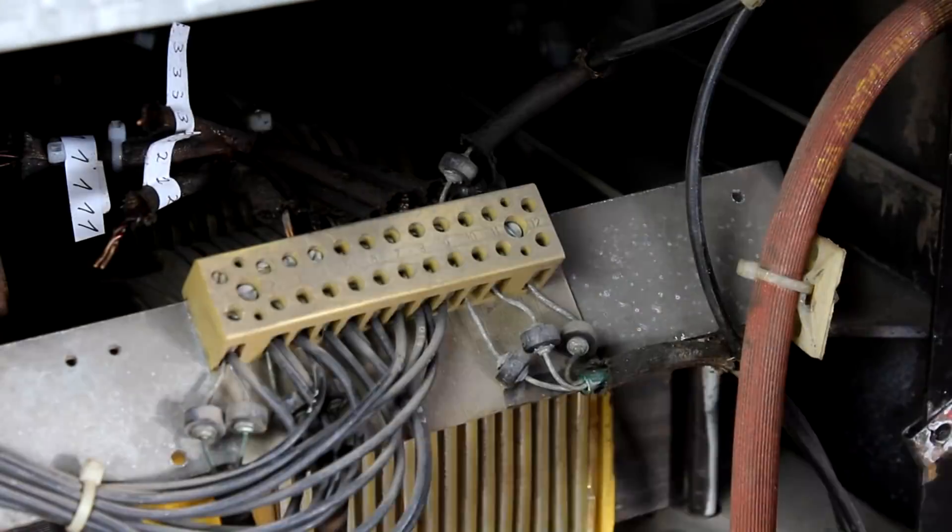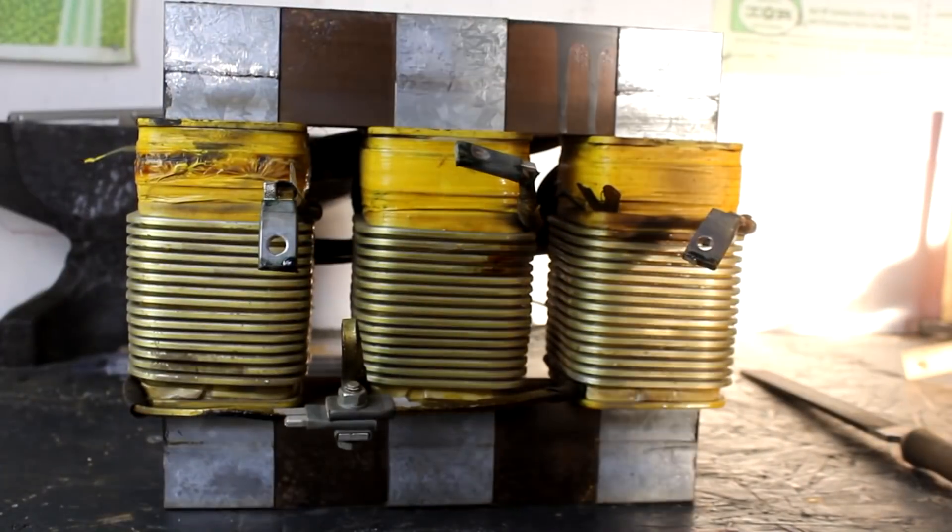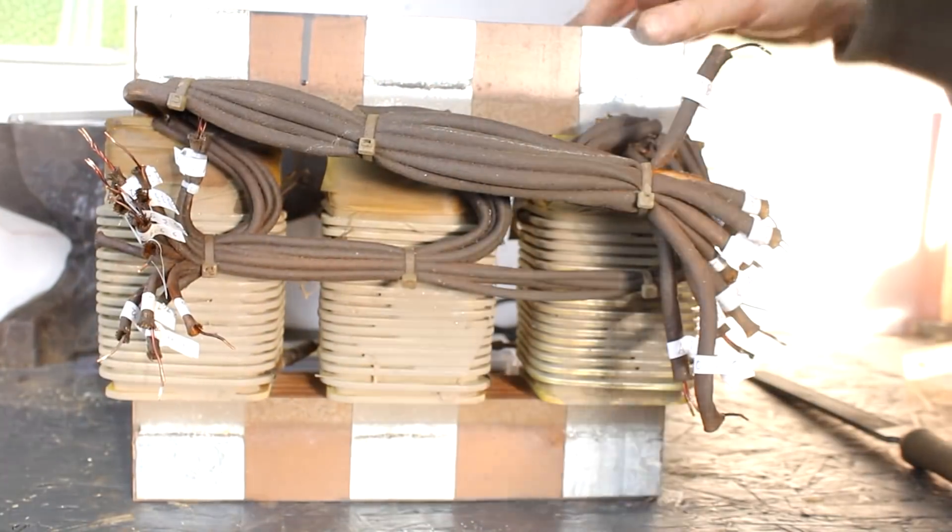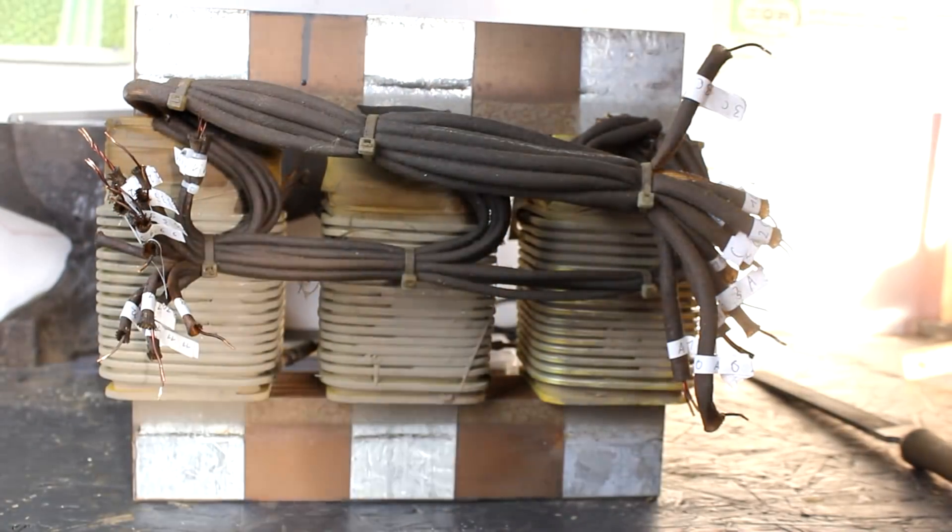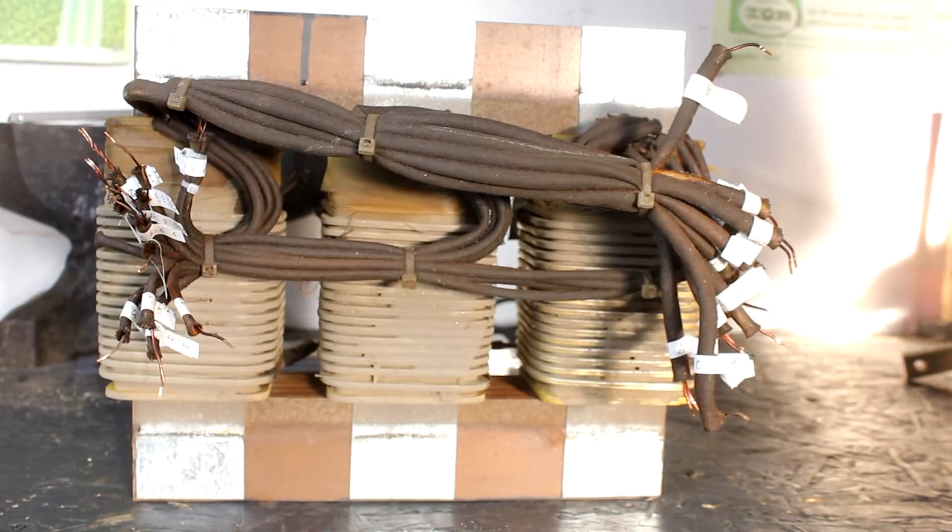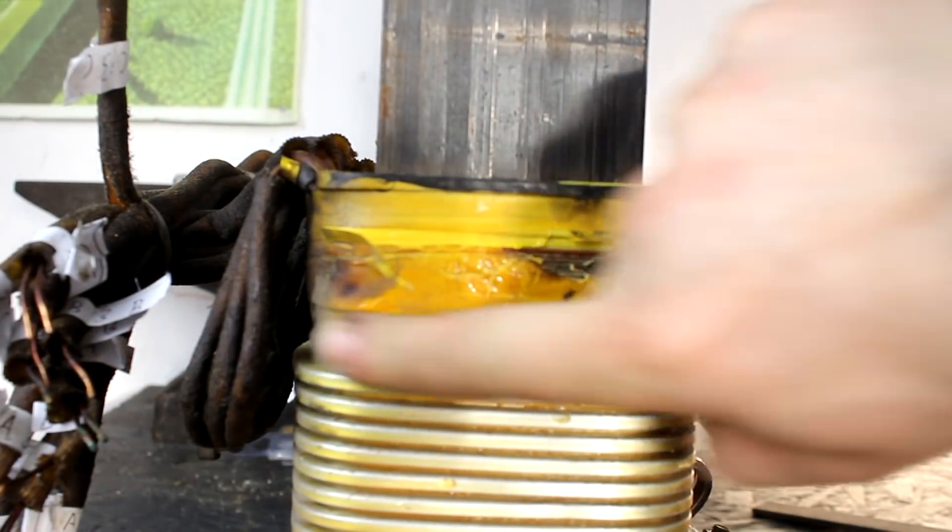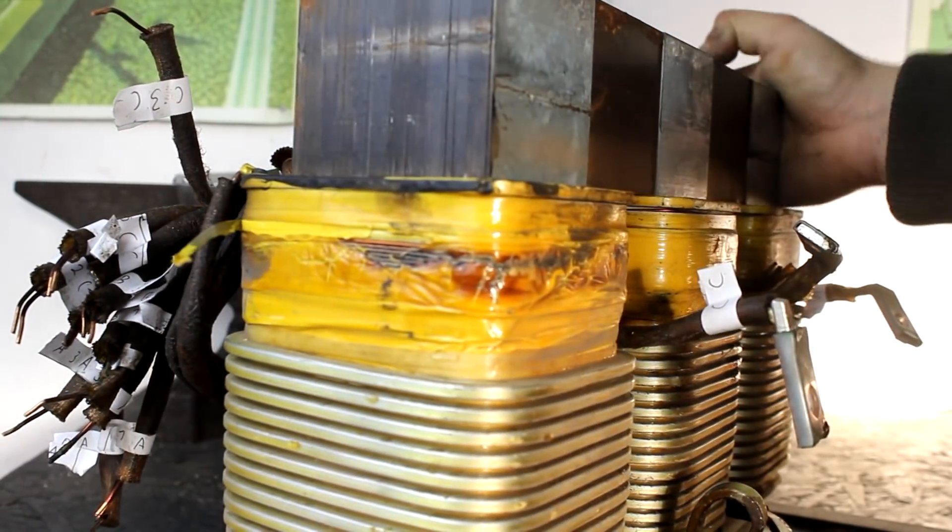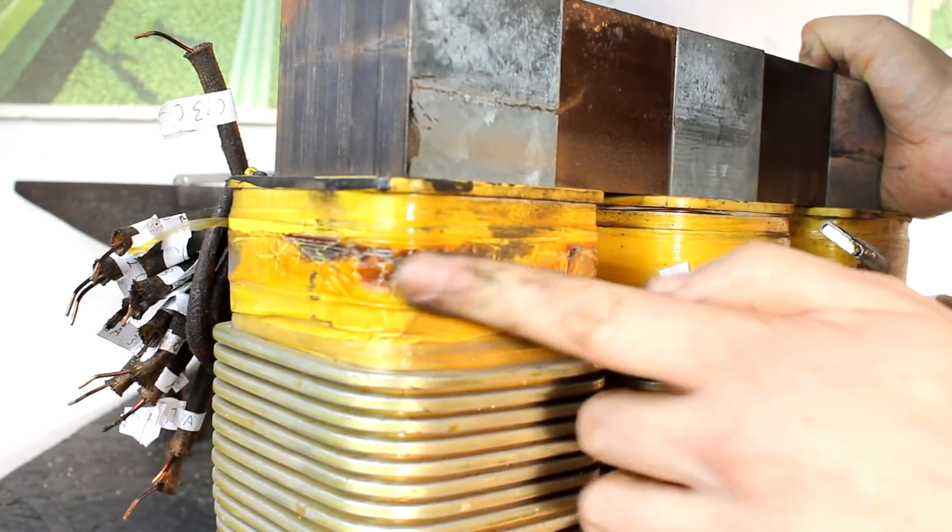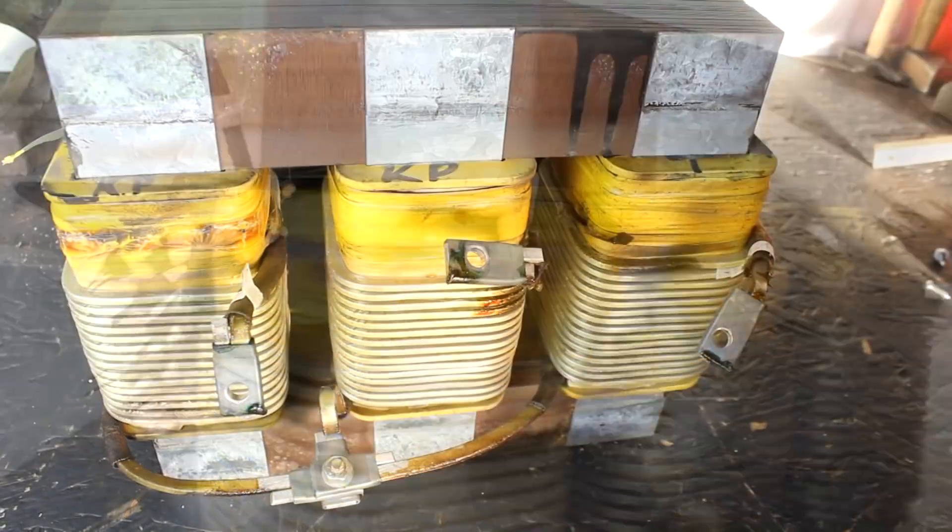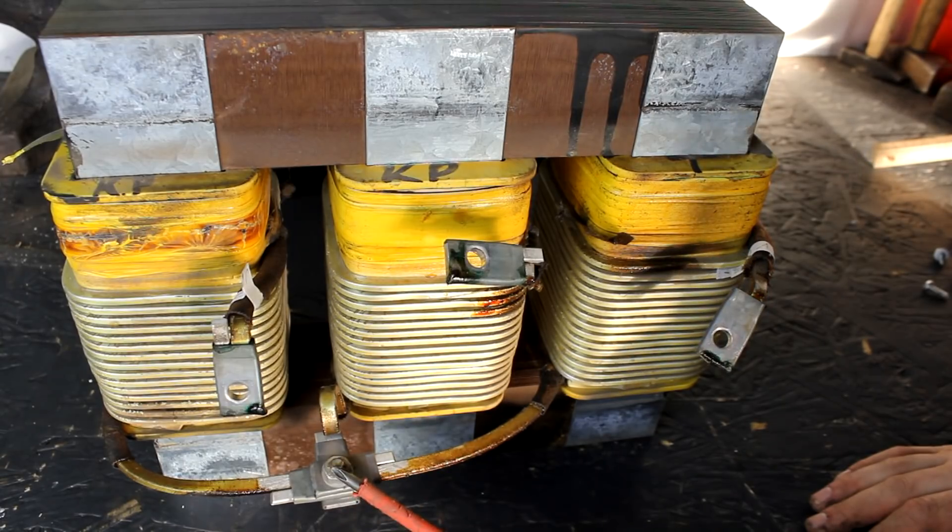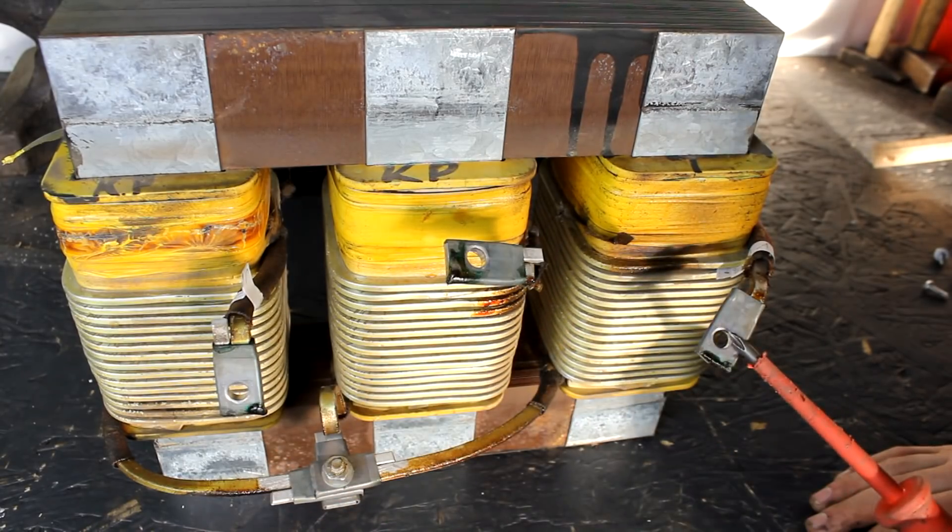So here is the transformer on the workbench. And we can see some of the damage and also the large number of secondaries and connections to the secondary. If we turn the transformer around, we can see that it's really that one spot where the tape is burnt all around that one leg of the transformer.